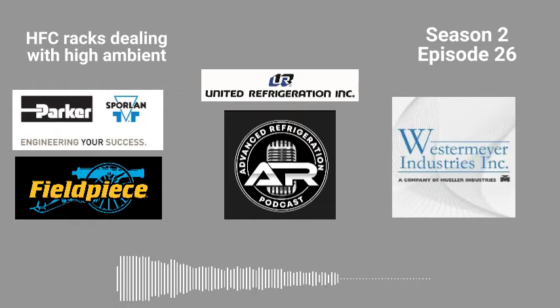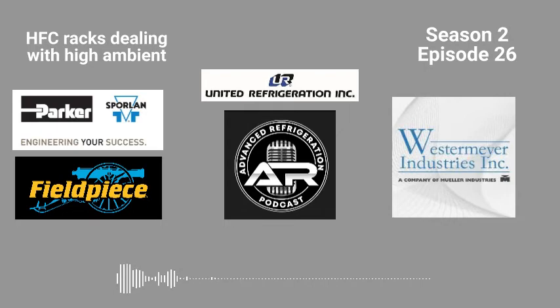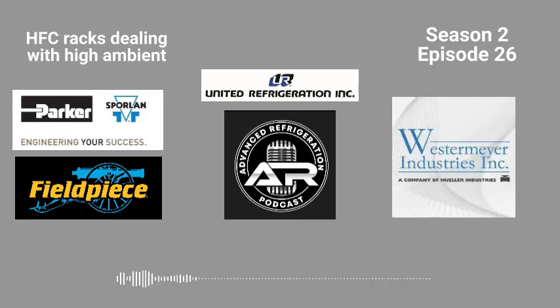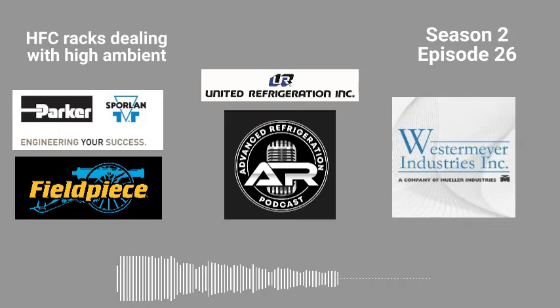So when I was back in Connecticut, we built these auto feeders. All it was, was a water solenoid hooked up to PVC with 2 hose fittings on the ends, and an A19 bulb that was activating the solenoid. So we'd strap the bulb directly to the liquid line. When the liquid line got up to 105 degrees, it would kick on the sprinkler, and then when it cooled down in the afternoon, it would stop the sprinkler.